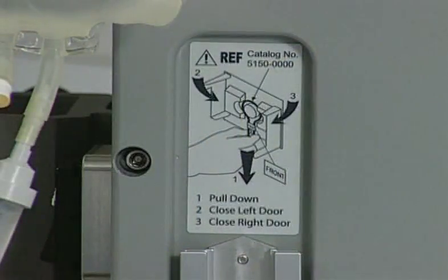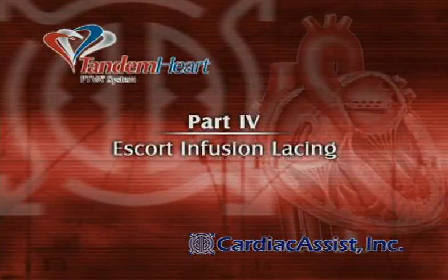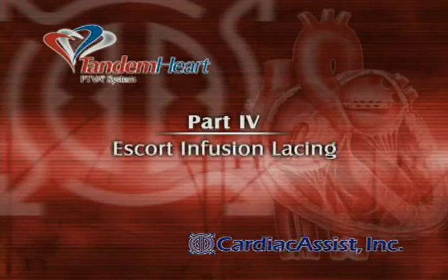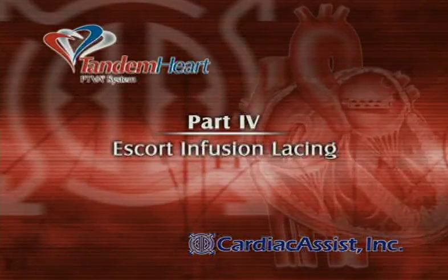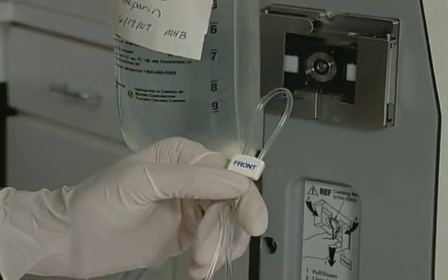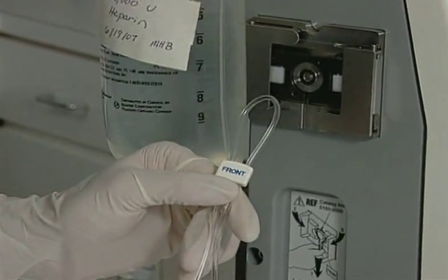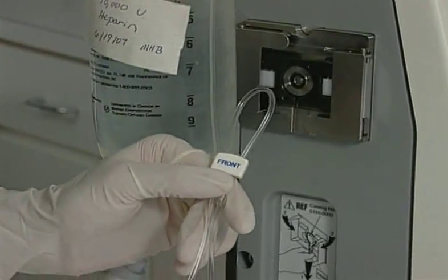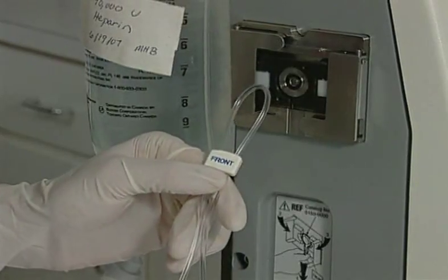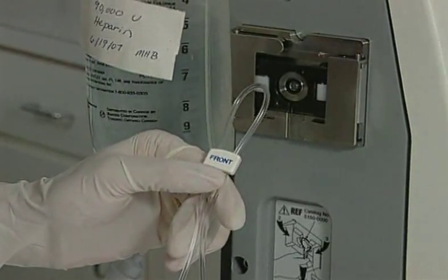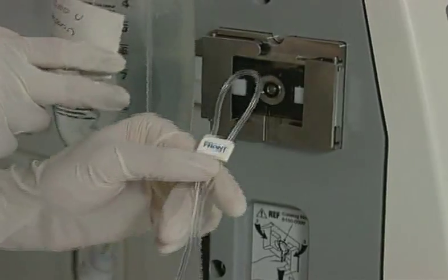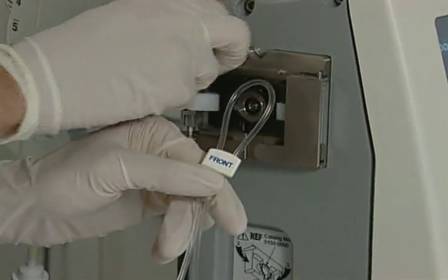The infusion tubing set must now be laced into the infusion pump on the controller infusion panel. Escort infusion lacing. Make a loop in the infusion assembly tubing so that the IV inflow is on the left and the IV outflow is on the right, or use the pre-formed loop in the infusion tubing with the word front located on the tubing guide facing toward you.